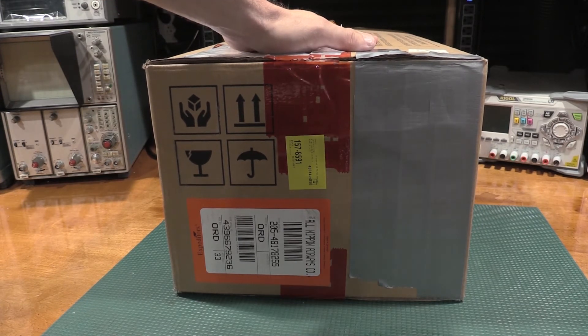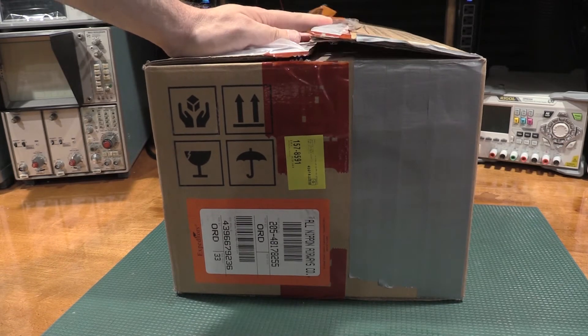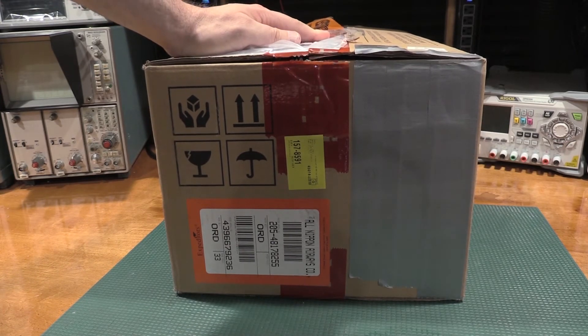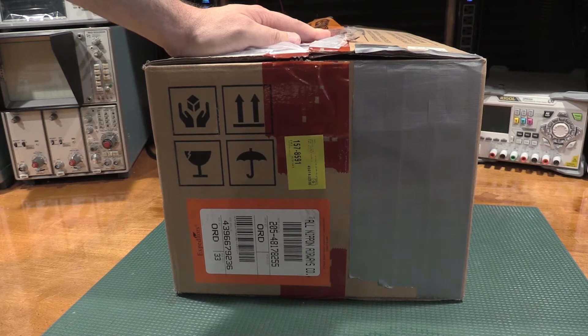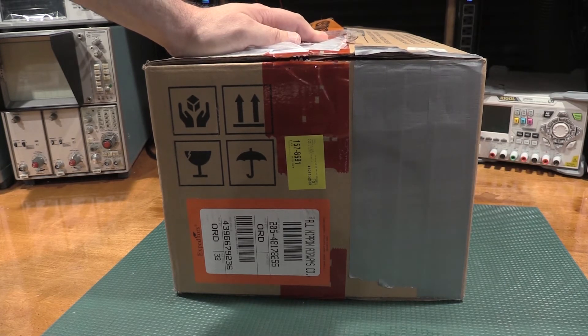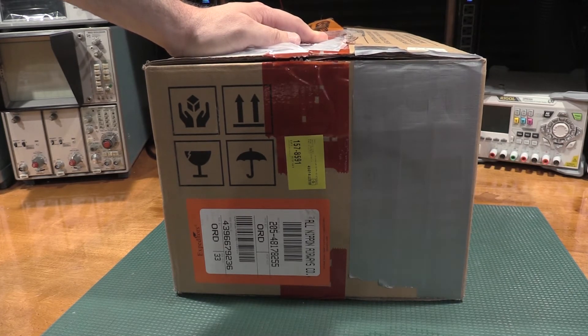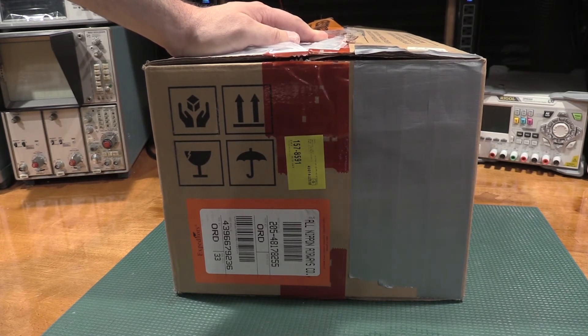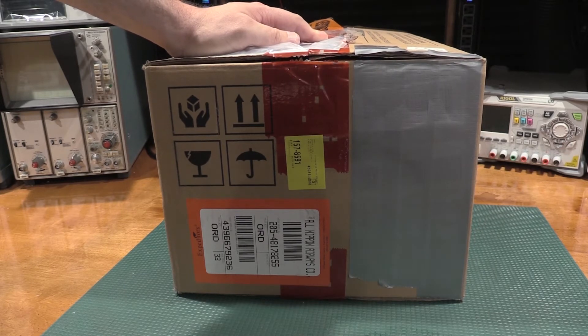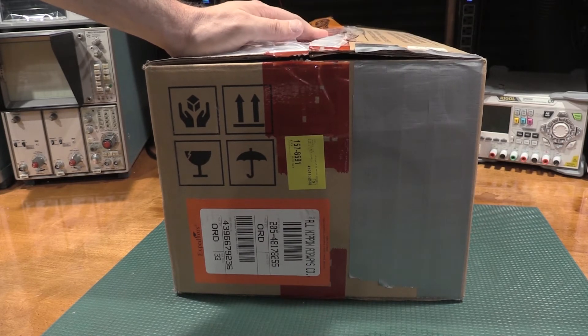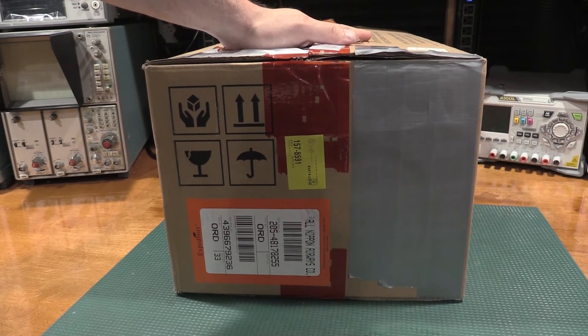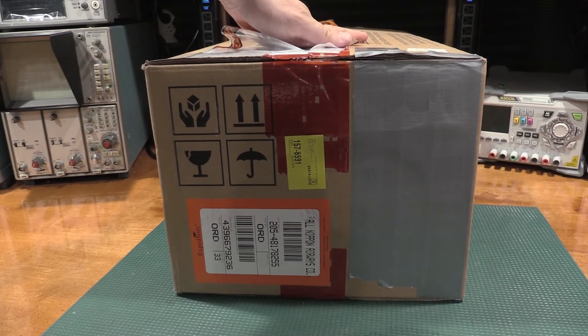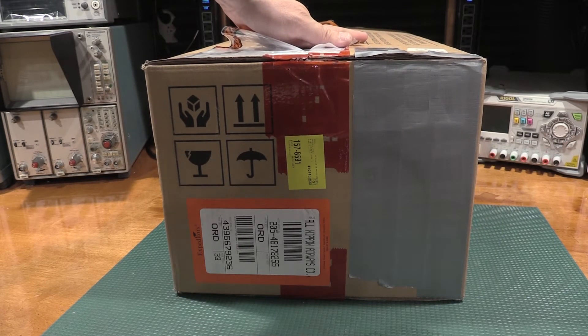One of the things you'll see with precision equipment, this is true for the 8.5 digits too, is when they're brand new, they'll drift around a little bit. And then, as they age, they'll really settle down and get stable. Keithley even says in the first couple of years, send them out once a year. And then, as it starts settling down, you can start extending that calibration interval. But I want to start getting some data on this meter. So it's still here. It's not broke or anything. Nothing blew it up. It just needs to head back to Keithley for a little bit.